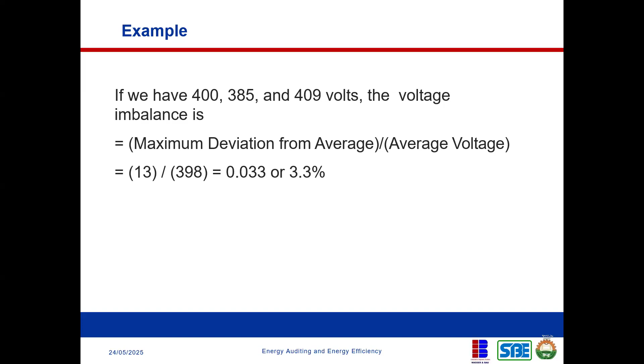So the highest deviation is 13. We take that highest deviation and divide it by the average voltage, 398. When we do that, we get 0.033, or 3.3%, which is high. It's significant and needs to be managed and balanced.